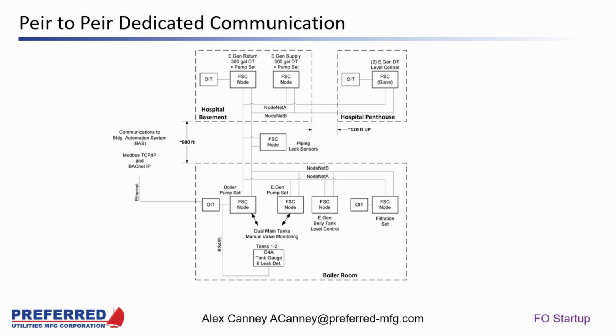As far as redundancy, Node B and Node A are both operating simultaneously. If we have an installation where the customer runs Node A and Node B up different sides of the building, and on one side we lose communication, say a forklift hits that line, we'll show an error for Node B loss, a NodeNet B loss, but the A side will continue to communicate. So it's really redundant, constant communication in two loops throughout the entire system. As for the communication protocol, my understanding is it's a modified Modbus protocol, built on the Modbus platform but modified with proprietary elements and tailored to the fuel application for our FSC controllers.